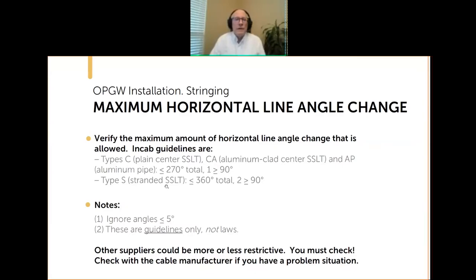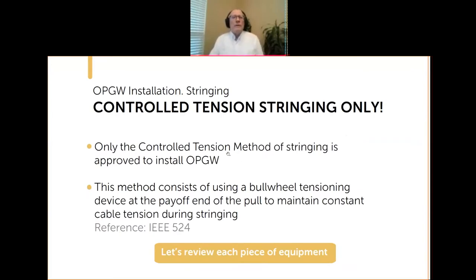Other manufacturers could be more or less restrictive, so you do need to check. But these are good guidelines because at the end of the day, cable is cable — they give you insight even if you're not working with InCab cable. For actually pulling in the cable, there is one and only one method to use: the controlled tension stringing method. This is also discussed in IEEE 524 and is what's typically used for conductors. This method consists of using a bull wheel tensioning device at the payoff end to maintain constant cable tension during the stringing.